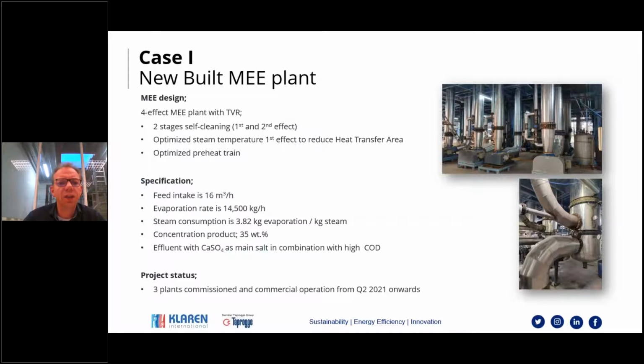Zooming a bit into this case in terms of design. In the design of this 4-effect plant, we have chosen to use a TVR. A TVR has some pros and cons. The most important is that a thermal compressor, the TVR thermal compressor, improves the energy efficiency, because you take part of the vapor from the first effect. In this case, it can also be the second effect, but we've chosen the first effect, and you use that to mix with the motive steam, as they call it, to generate a mixed steam flow for the first effect. And since you use part of the vapor generated, this is an optimum energy configuration, which in fact you will also see in the MVR. But I will talk more about that later.